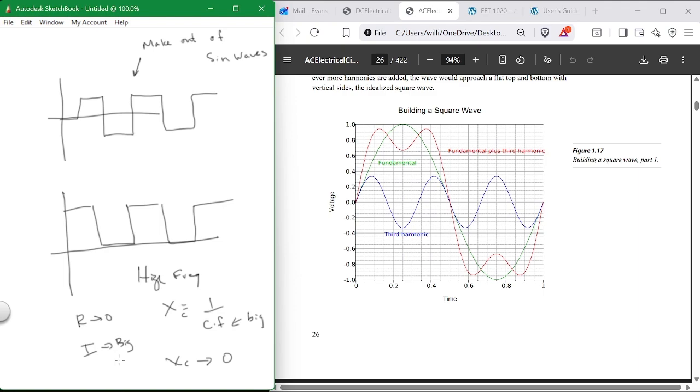So up in 2350, I had these tanks, tank over tank, and I got a bilge pump, and I was hitting them with a signal like this. There's a little capacitor in that bilge pump that acts as a kind of smoothing device. If you were to run a bilge pump with a straight 24-volt signal, it would work perfectly.